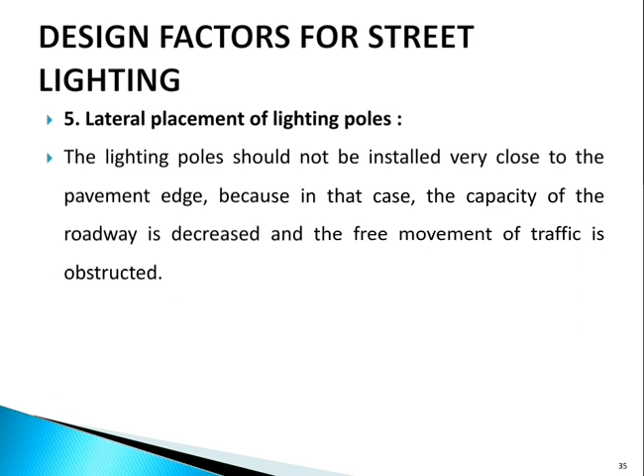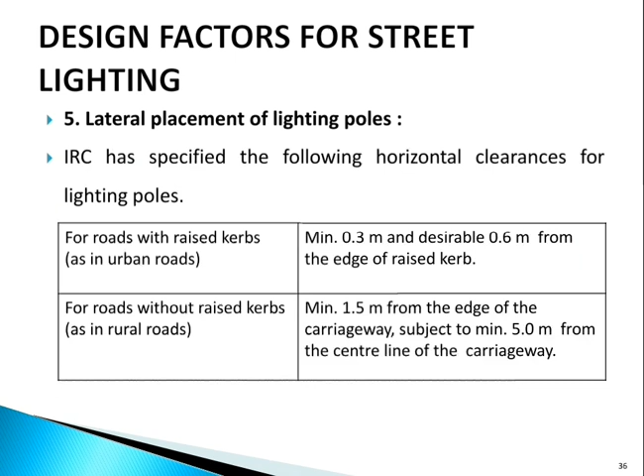So IRC has specified the following horizontal clearance for the lighting poles. For roads with raised curb, as in urban areas, minimum 0.3 meter and desirable 0.6 meter from the edge of the raised curb, whereas for roads without raised curbs, as in rural roads, minimum 1.5 meter from the edge of the carriageway, subject to minimum 5 meter from the center line of the carriageway.